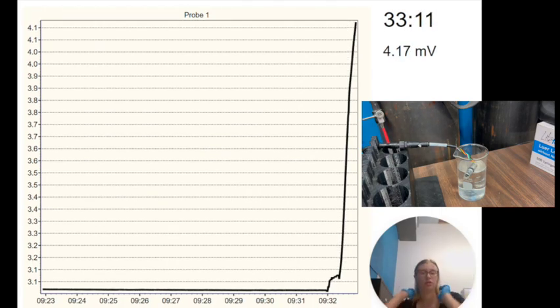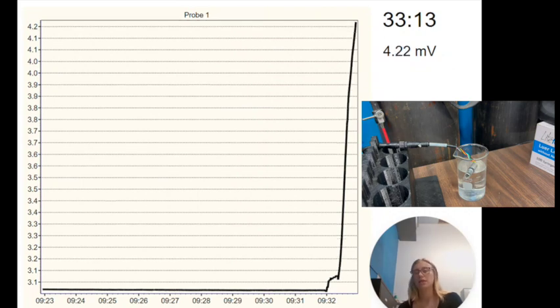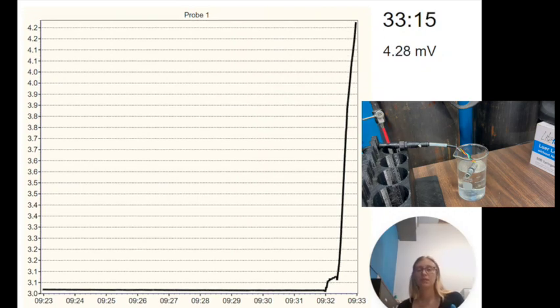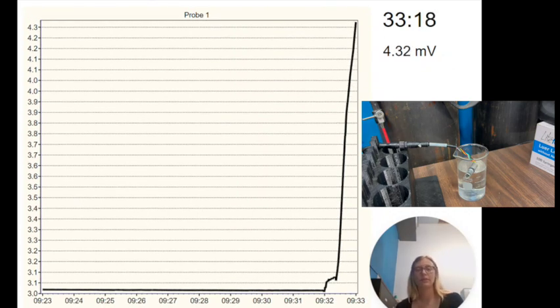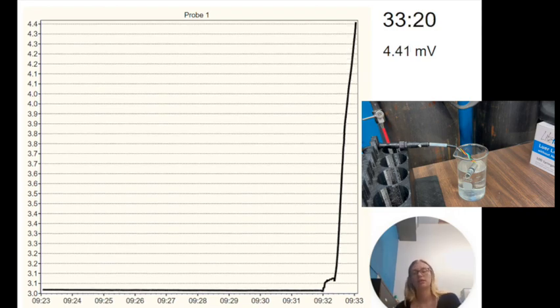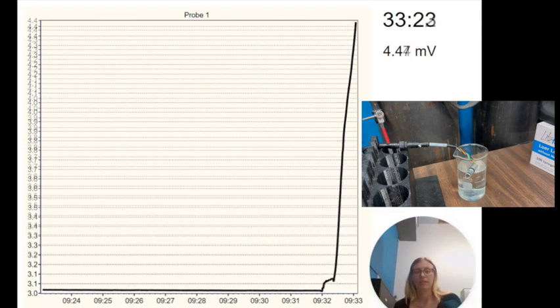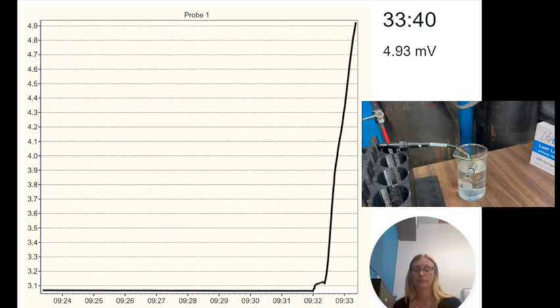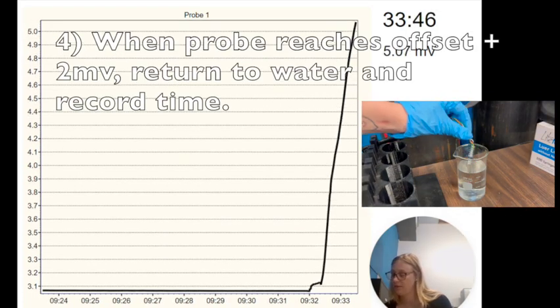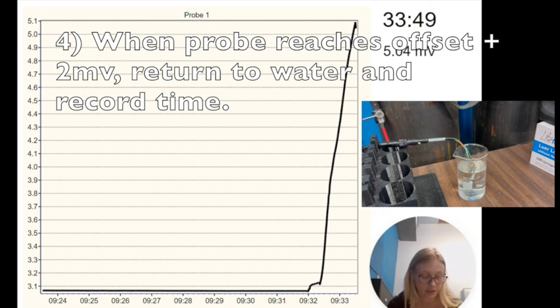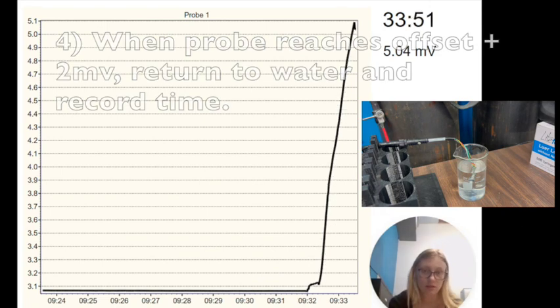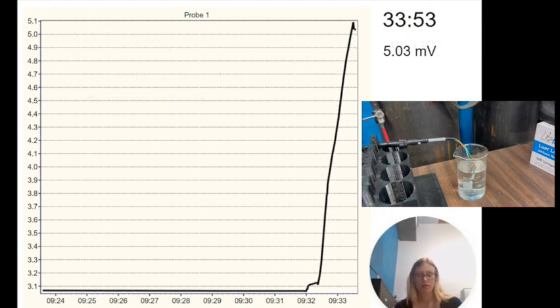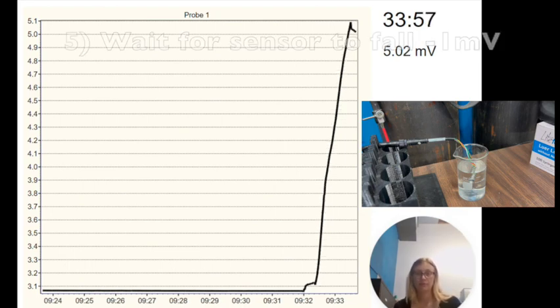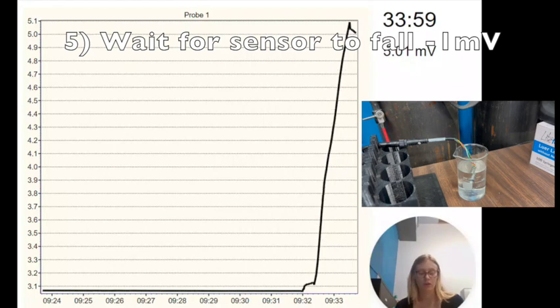It's important to watch the readout really carefully when you're doing this, because the sensors can cavitate if they dry out too much. So I'll show you what that looks like, but we want to be paying attention. Okay, we're going to put it back in water at 33:45. And now we're going to wait for it to fall 1 millivolt.